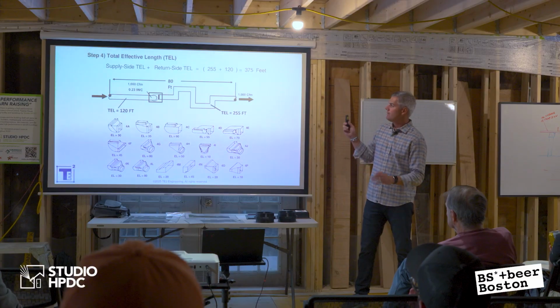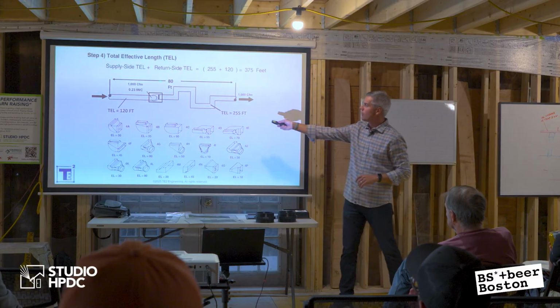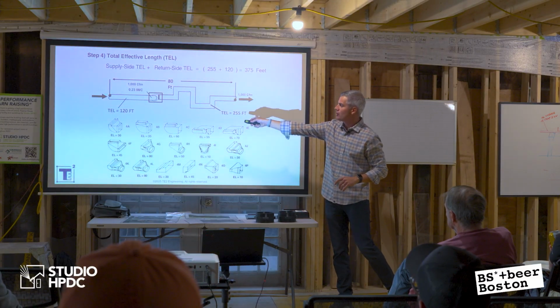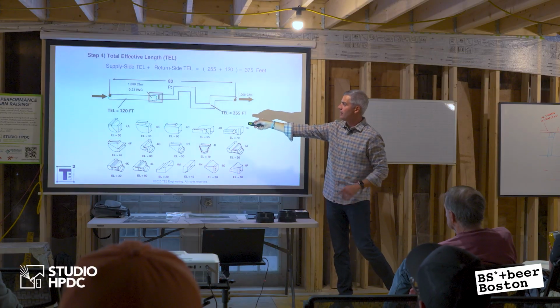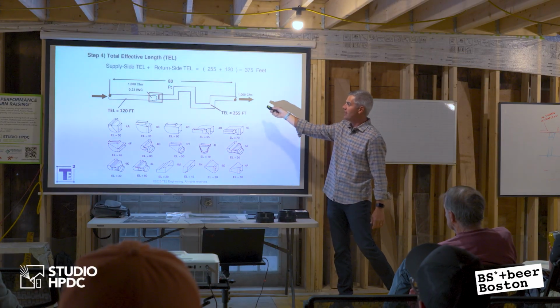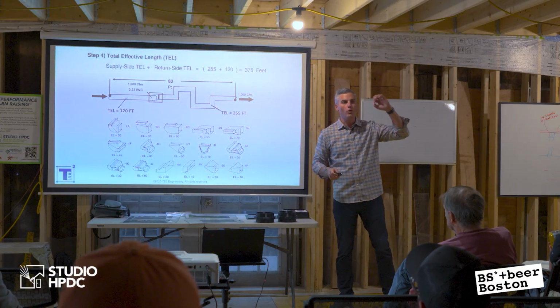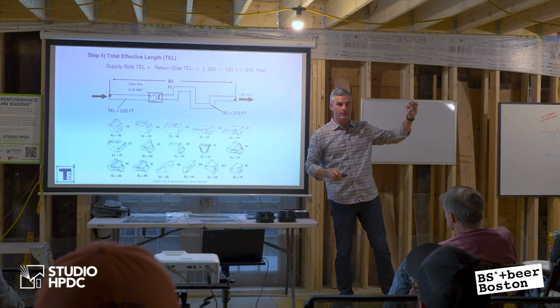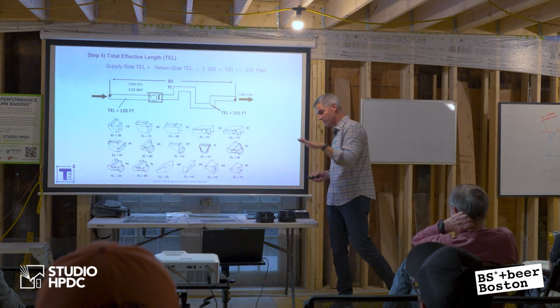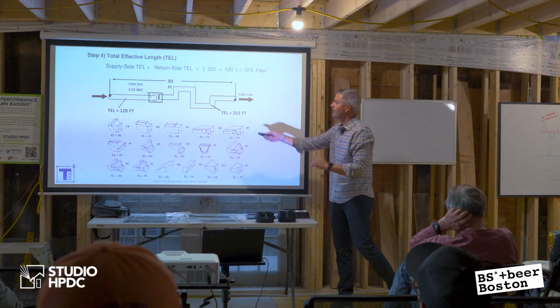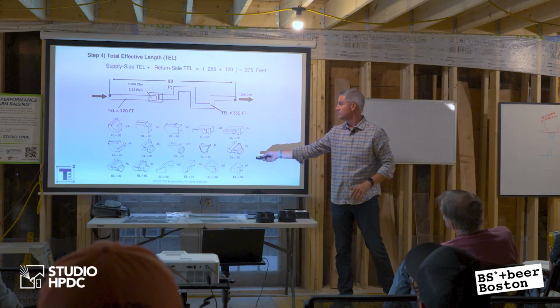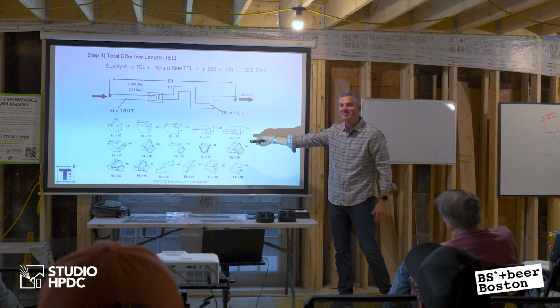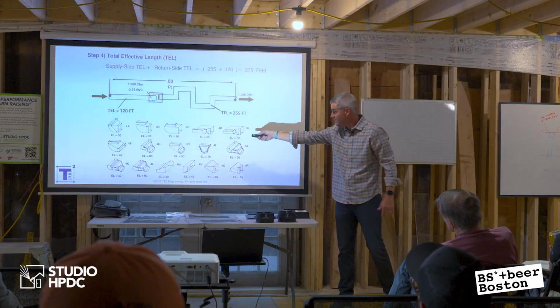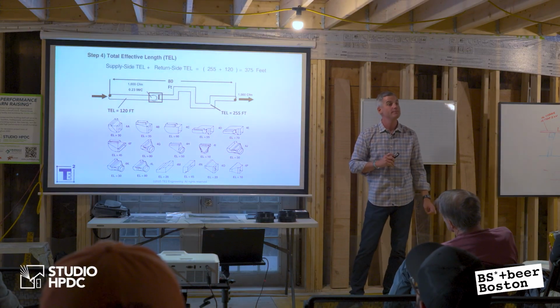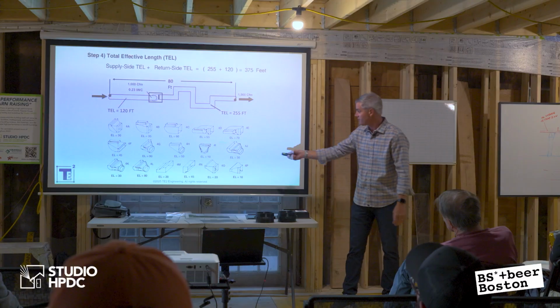And another point that I want to make is the ductwork might be 80 feet in length from return to supply. Here's my blower, right? Here's my return duct, here's my supply duct, I run 80 feet. We're talking about total equivalent length of feet, not 80 feet as the crow flies as I trace the line. I have to add up all the fittings. If I use a crappy fitting, that's 60 equivalent length of feet. That fitting represents 60 feet of straight duct. This fitting right here, 30.